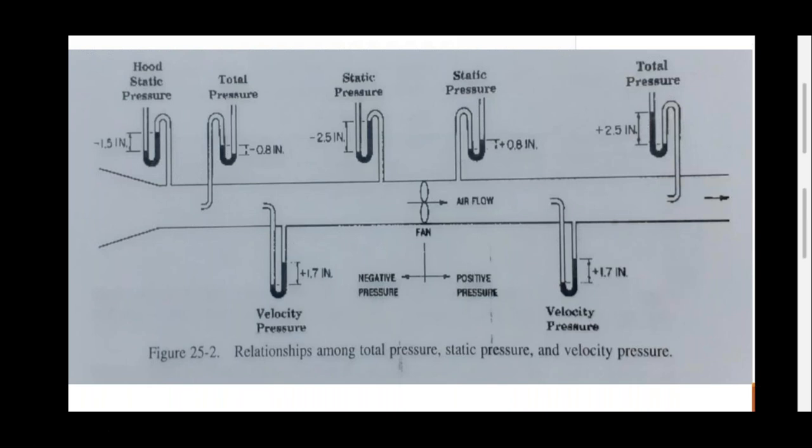So my question is that. We can measure total pressure in two ways. For example, we measure static pressure here, and then we measure velocity pressure, and then we apply the formula, we get total pressure. And there is also a manometer with the position of the tube like this. Here we also get total pressure. So both pressures ideally should be equal. Due to some losses, there may be a minor difference, but theoretically these pressures should be equal. Thank you. So nice, sir.